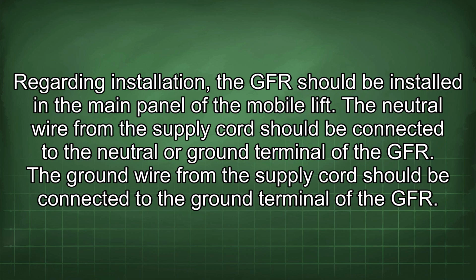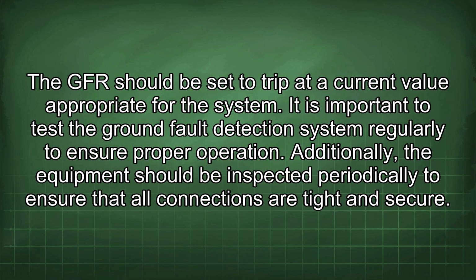Regarding installation, the GFR should be installed in the main panel of the mobile lift. The neutral wire from the supply cord should be connected to the neutral or ground terminal of the GFR. The ground wire from the supply cord should be connected to the ground terminal of the GFR. The GFR should be set to trip at a current value appropriate for the system. It is important to test the ground fault detection system regularly to ensure proper operation. Additionally, the equipment should be inspected periodically to ensure that all connections are tight and secure.